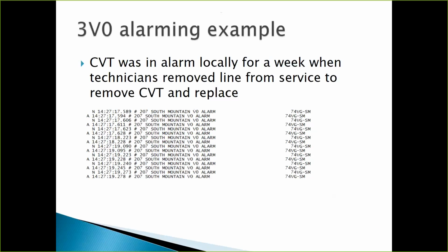This is an example where we had a CVT that was alarmed locally for a week, a zero sequence alarm. This is the event recorder that it was printing out. It's telling you it had a 74 alarm, voltage, ground, and SMs for the South Mountain. This is just one snapshot of the event recorder paper. It literally ran paper, just ran page after page after page. It kept alarming. Look, it was alarming every few milliseconds. So this is an example where the zero sequence alarming actually caught an event prior to the catastrophic failure, and we call this a success.